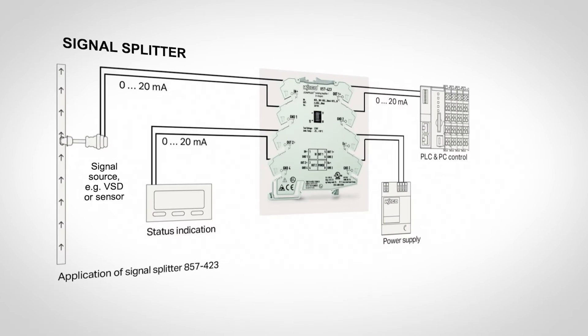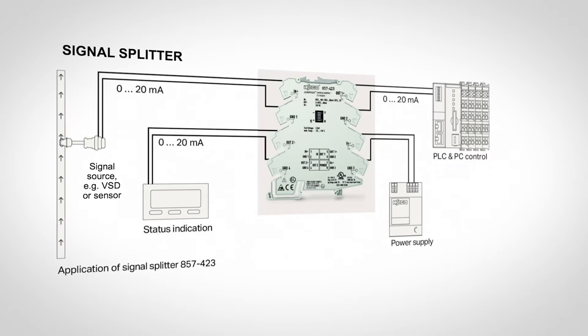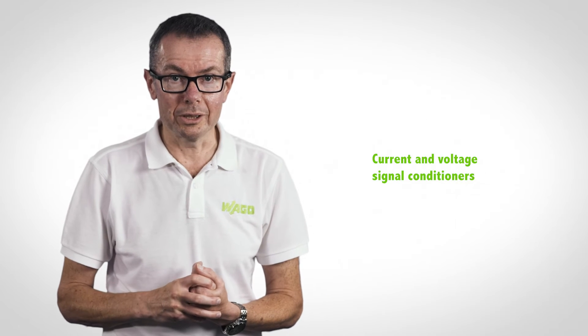Signal splitters: these do exactly what they say. For example, should it be necessary to send a 0 to 10 volt or 4 to 20 milliamp analog signal from a variable speed drive to both a PLC and an HMI simultaneously, a signal splitter can be used. It has the added benefit that all three pieces of equipment are electrically isolated.